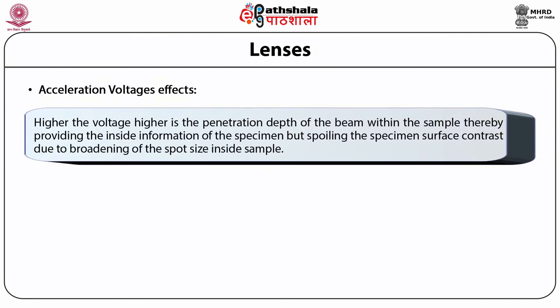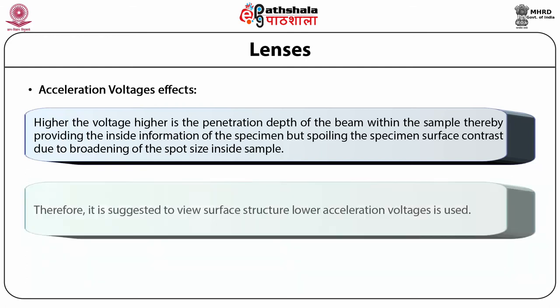Let us now discuss about the acceleration voltage effects. Higher the voltage, higher is the penetration depth of the beam within the sample, thereby providing inside information of the specimen but spoiling the specimen surface contrast due to broadening of the spot size inside the sample. Therefore, it is suggested that to view the surface structure, a lower acceleration voltage should be used.